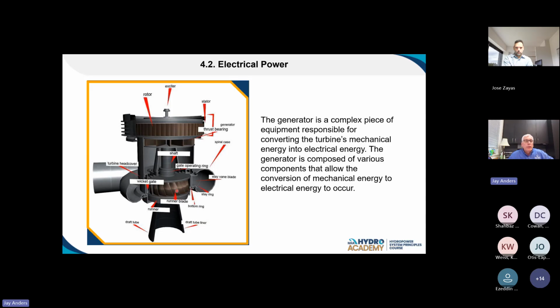It's the governor that controls the position of these wicket gates. These wicket gates all operate in tandem. Tandem may not be the word; they're in unison. There are several of these, and they're all connected via a servo motor. We don't have one shown, so you really can't see it. The servo motor is what connects up to the governor. It goes in an open and closed fashion. Those servos work to position the wicket gates at any particular position along the way, so they can go from fully open to fully closed.